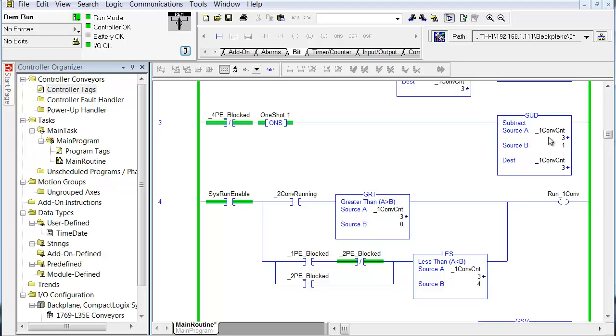And then another accumulator that would accumulate all of the cartons that went onto 2 conveyor. Then at the end of the shift, I would look to see how many were still on one conveyor. And I would do a little math to make sure that the numbers balance. So I'd create, if you want, a virtual balance sheet. And typically, you do that all the way through the system to see if you're actually missing any cartons, because it's easy for an employee to come by and see that there's something wrong with a carton, that it's torn or damaged, and pull it off of the conveyor and set it on the floor so it doesn't go into the system, and then forget to go over to the HMI and then correct it in the virtual system that's in the tag database.